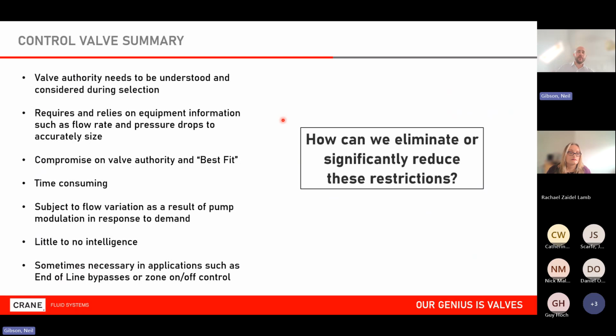To a certain degree, the reason I've explained that is to highlight the concerns, the difficulties, the challenges we might face when using control valves. A typical standard 2-port control valve: we need to understand the valve authority. We need the equipment information. If we don't have the flow rates and pressure drops, we're second guessing ourselves. It's never perfect. It's a best fit. It's time consuming to balance the system. It's subject to flow variation as the pump modulates its speed. If we don't put in things like DPCVs, it's little to no intelligence, and sometimes when we do need to use them for zone or end-of-line bypasses.